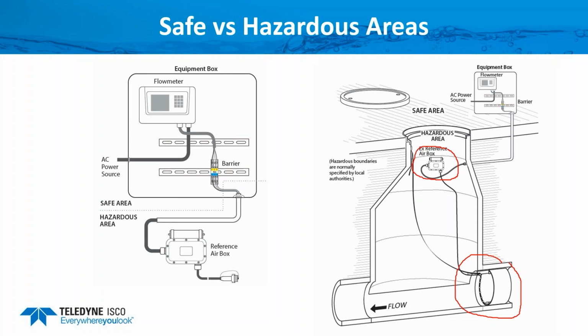Taking a closer look at that, here's our air reference box, with desiccant on there to reference to atmosphere. It goes through a barrier. Now the barrier can be mounted on a DIN rail mount next to your controller, or you could put it in another type of enclosure, but it needs to be separated from the actual electronics itself. And again, you can just refer to the control drawing out of any of the manuals to help you out with this.